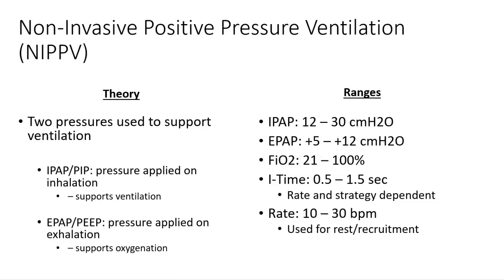Also, in relation to FiO2, you can increase your EPAP depending on your FiO2. I time, we'll either have between 0.5 seconds or 1.5 seconds, and this is dependent on rate and strategy. So if you have a rate of 30, you're not going to have a 1.5 second I time, or else that's not going to allow accurate time for exhalation. But if you have a rate of 10 and you're just working on recruitment or hopefully transitioning from Nippy to a CPAP, you can give a longer I time, such as 1 second. I found that most of the time 1 second is a great place to start, and then I can adjust up or down from there.